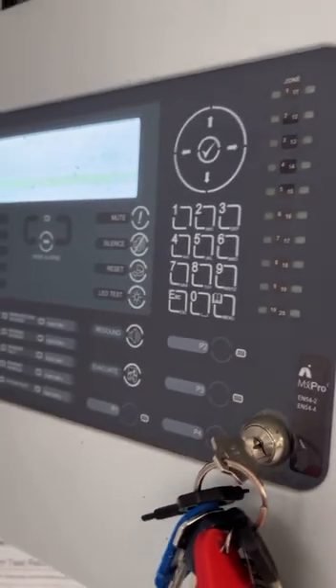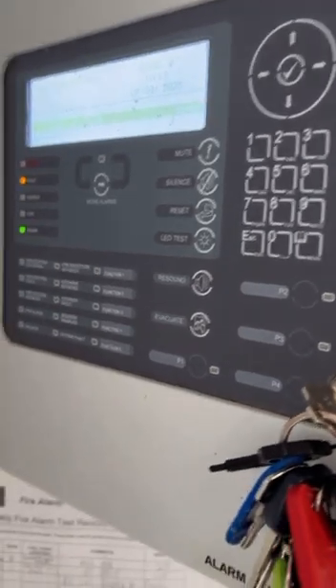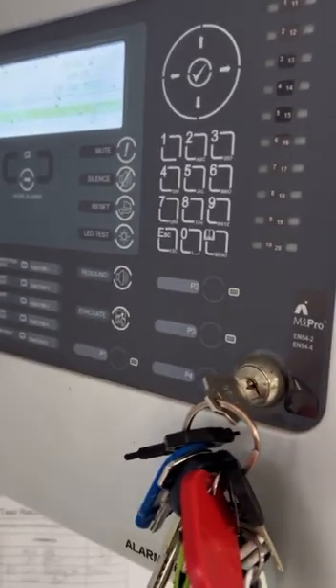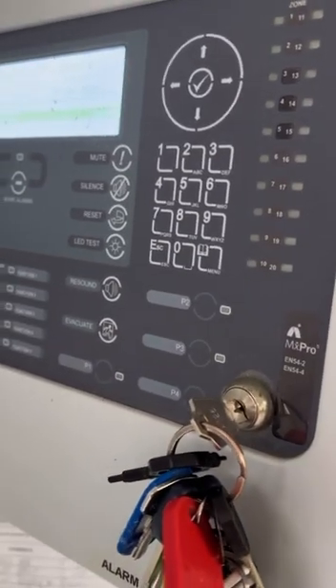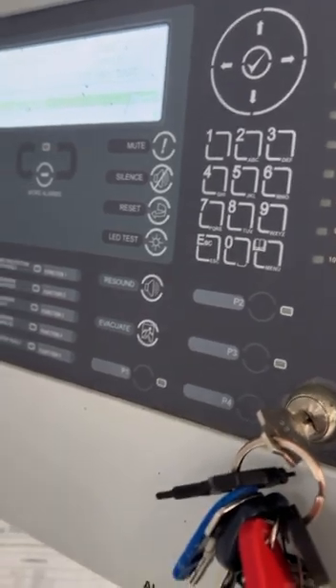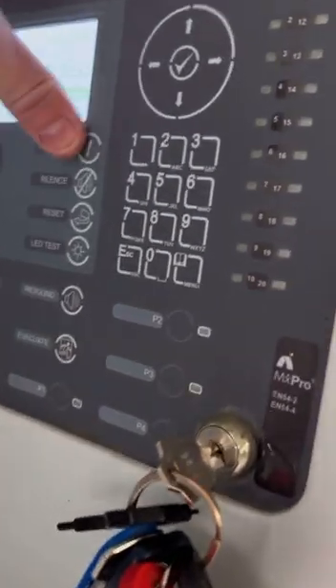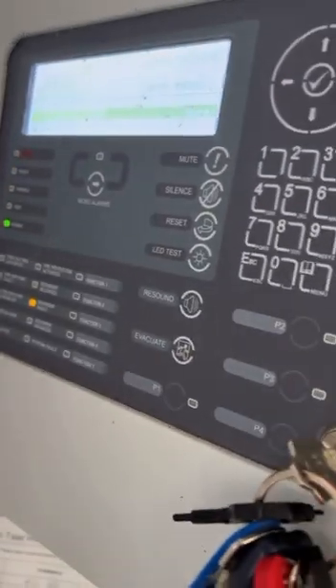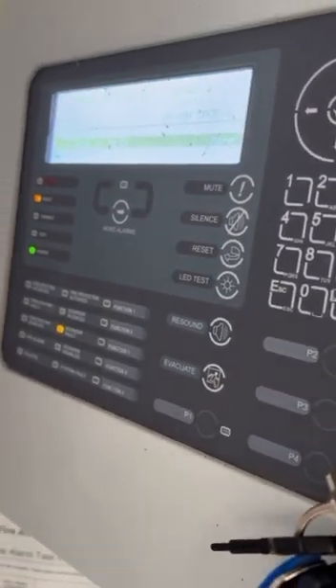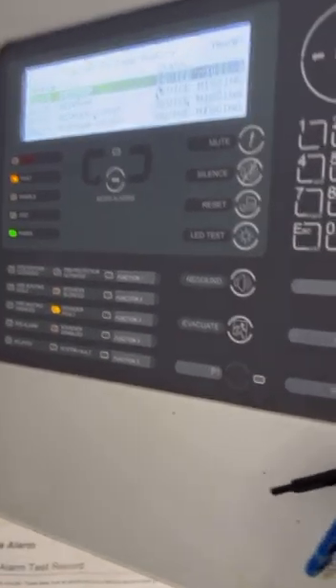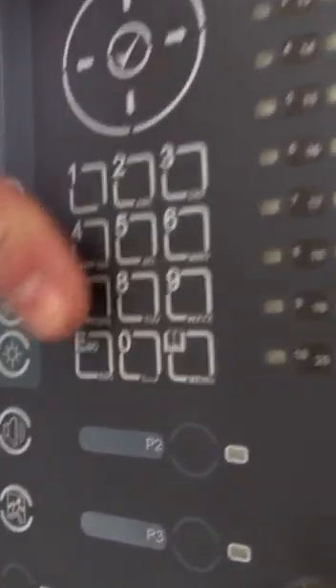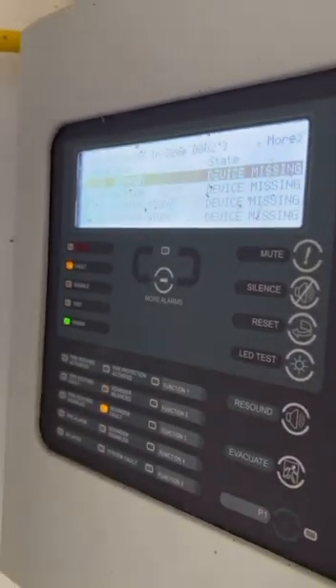Just double check what I do lose. Five zones in fault when I disconnect that leg of the loop, but it could just be that there's a couple of devices on that zone lost but then the rest are still there. Like pantry attic could be on that zone. I'd only be losing my room when that happens.